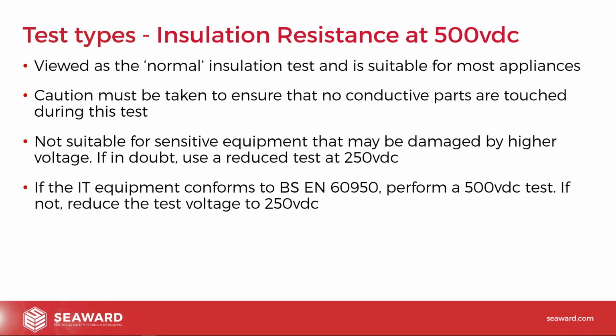I know people who've tested at 500 volts every day for years and years and never had a problem. I also know people who've damaged equipment by doing that test. It's a very, very rare occurrence, but you do have to be careful because the 500 volt test is technically capable of damaging some equipment in very rare cases. Although it is seen as the standard test, generally we'd apply it to the normal stuff: your kettles, your toasters, your leads, your drills. But if you've got an expensive server rack or an expensive PC, you might think, we'll do a 250 volt test on this instead, just because it's safer for the equipment that way round.